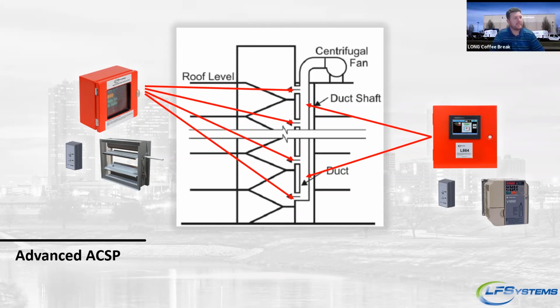So where do life safety dampers come into play regarding the multiple point injection system? To me, it looks like we wouldn't need as many life safety dampers, and at each injection point, we'd actually provide your IPR dampers. Does this system reduce the amount of life safety dampers needed? It absolutely does. So basically, you would have a fire smoke damper on the inlet of the fan, like I said, to keep smoke from circulating back into the shaft or the stairwell. But then after that, at each injection point, you wouldn't have a fire smoke damper. You would use our IPR damper instead.